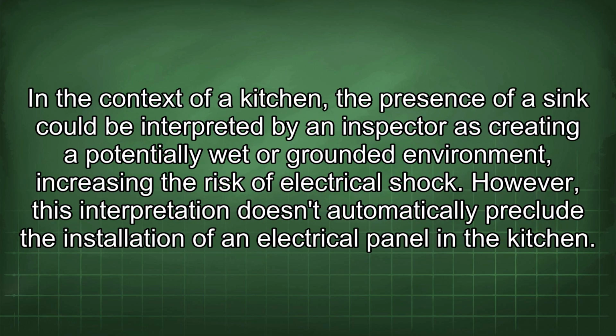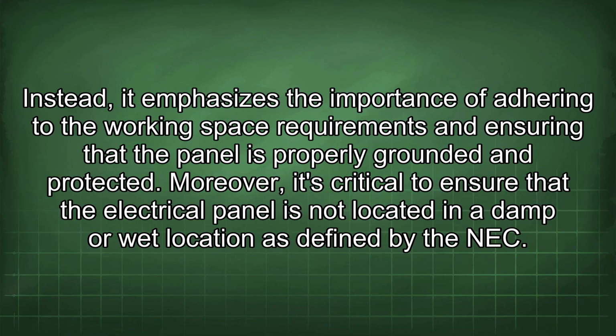In the context of a kitchen, the presence of a sink could be interpreted by an inspector as creating a potentially wet or grounded environment, increasing the risk of electrical shock. However, this interpretation doesn't automatically preclude the installation of an electrical panel in the kitchen. Instead, it emphasizes the importance of adhering to the working space requirements and ensuring that the panel is properly grounded and protected. Moreover, it's critical to ensure that the electrical panel is not located in a damp or wet location as defined by the NEC.